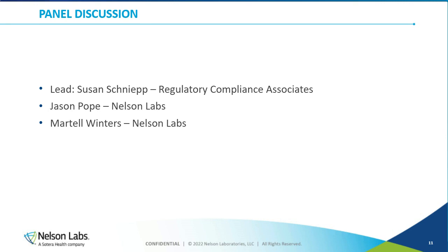It's interesting that sometimes we can get the idea that sterilization takes care of everything, but there are actually quite a few aspects of product where sterilization really is not beneficial. The main three that come to my mind are, from a biocompatibility standpoint, sterilization usually plays little to no role in the biocompatibility of a product. Bacterial endotoxin, in most cases, sterilization processes do little to nothing to reduce those.